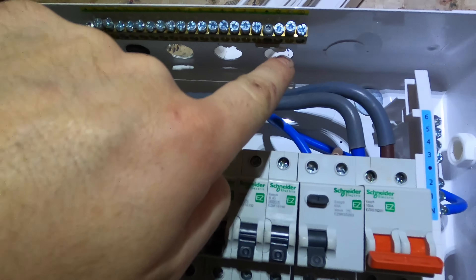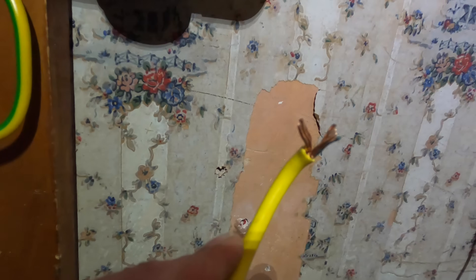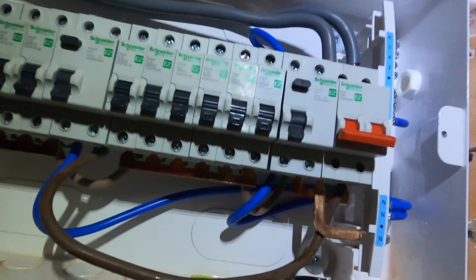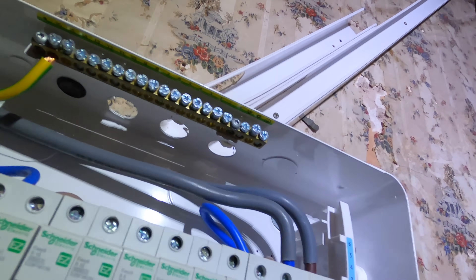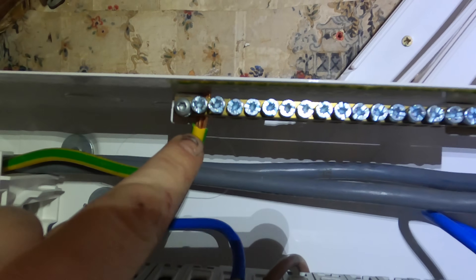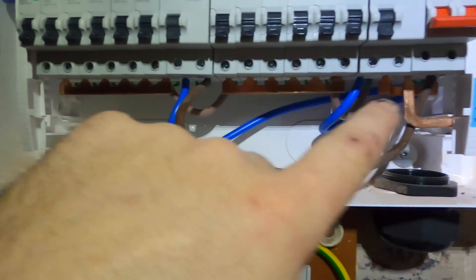I uploaded on my Instagram - to be fair, good effort. But look at this: I've just literally pulled it out and only half of that was actually connected. I've never used one of these Schneider boards before - they look like a decent board and the terminals are massive, so there's plenty of room. There's no excuse whatsoever. All of these are like this, just barely connected. And the cover that covers the busbars is literally smashed - it's all hanging off.